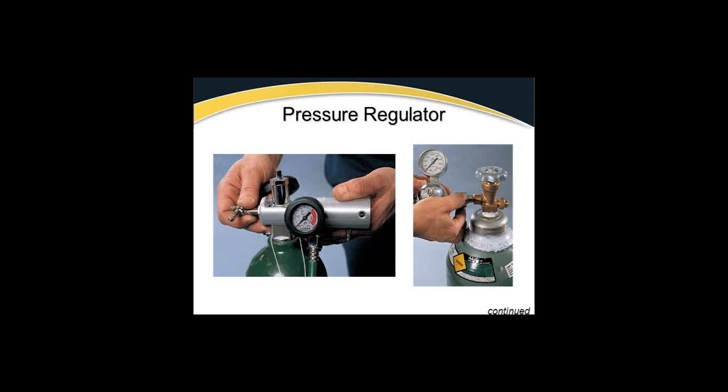On there you see the oxygen bottle in picture number 5. There are 3 holes in the neck of that. The bigger hole is where the oxygen actually flows through. The 2 lower holes are what's called a pin system, and those pins are pin number 2 and pin number 5, out of a total of 6 potential spots to place those. Pins 2 and 5 correspond to oxygen.